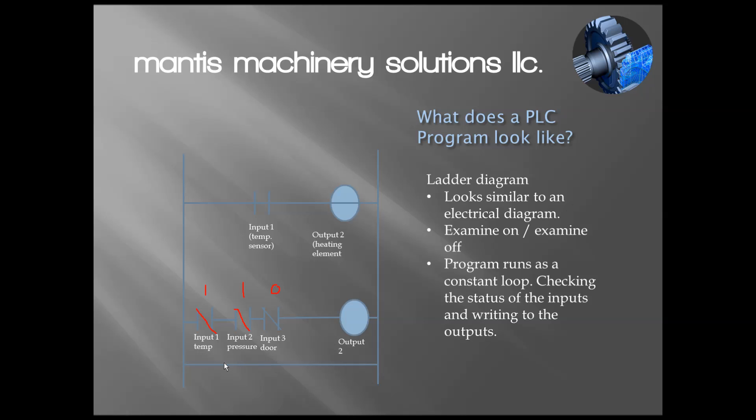I can get more complicated. Here, to produce output number two, I've added a couple extra things. Input number one would have to be made to close this, input two would have to be made to close this, and then input three would have to be not made or have a zero. So I'd be looking for a one and a one and a zero. If those three conditions are made, then I've completed my path of current and output number two turns on.